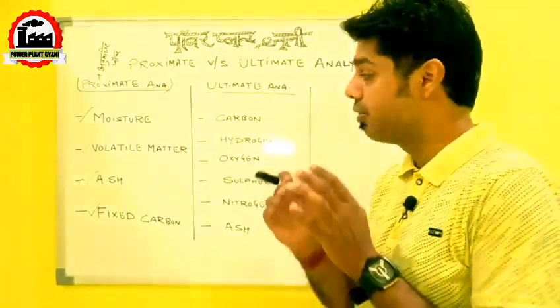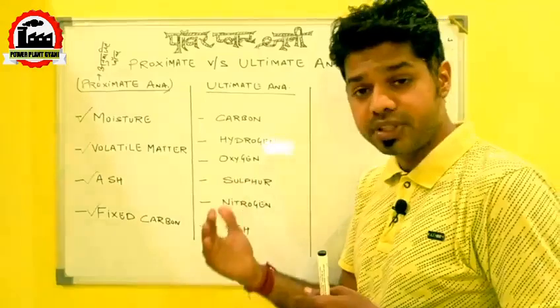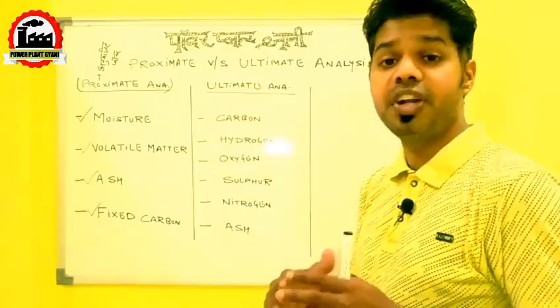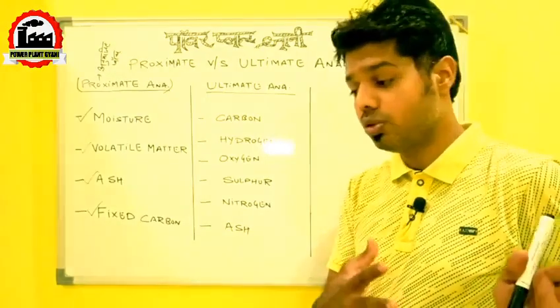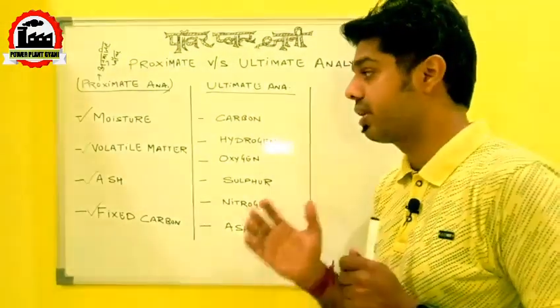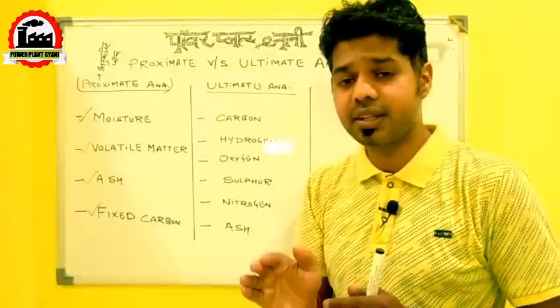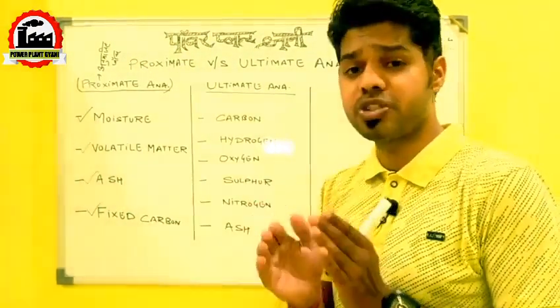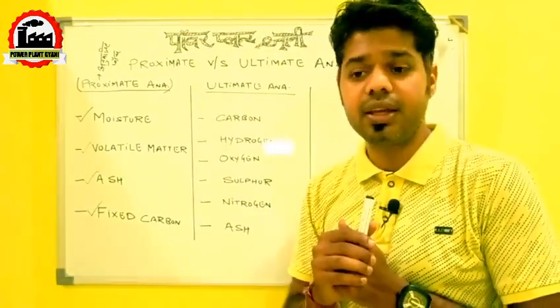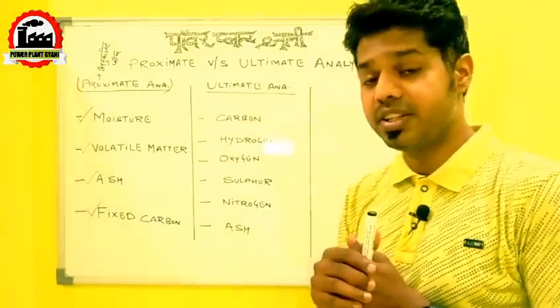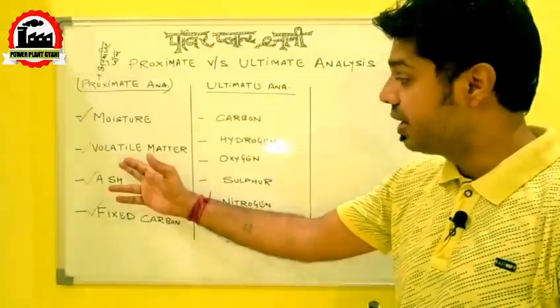What is moisture? Moisture is the water content in the fuel, which is undesirable. If you have more moisture in the fuel, it will increase the handling cost and the transportation cost because it adds to the weight. Moisture also requires heat energy to evaporate, so the vapor carries away heat, which reduces the total heat-releasing quantity of the fuel.